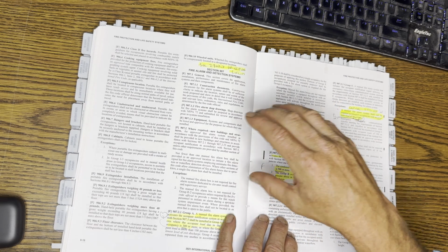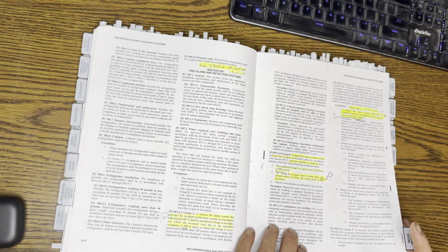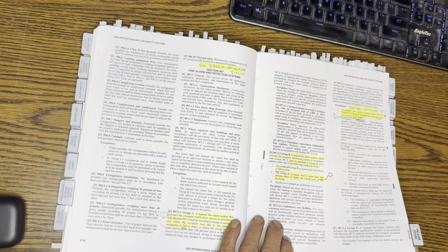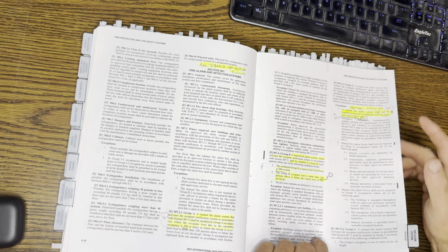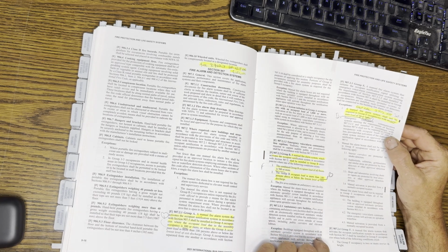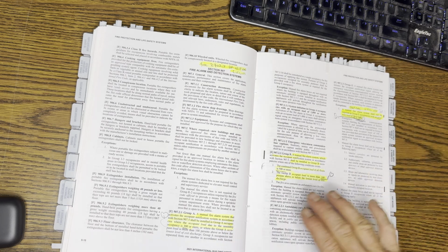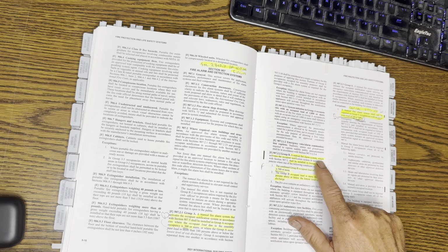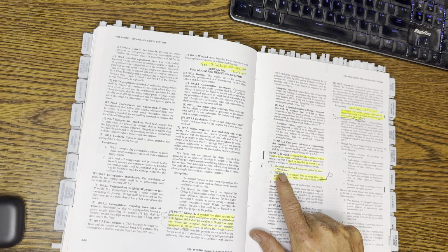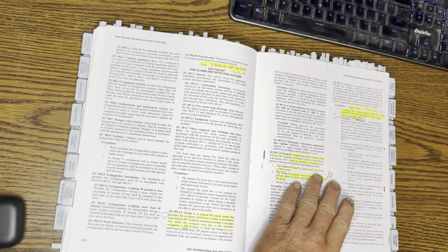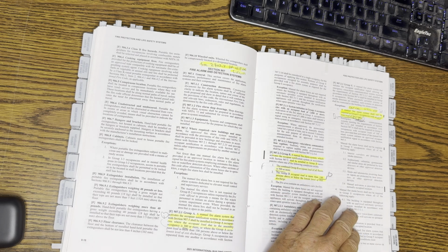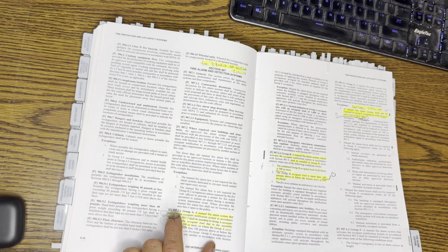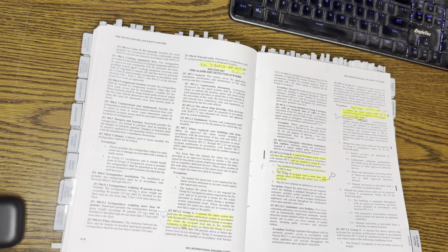A fire alarm system that has individual smoke detectors. And they can all be tied together. If you sense smoke anywhere, then all the signaling devices, the strobes and the alarms go off throughout the structure. So this just tells you where you need it. You don't even need any kind of a fire alarm system, any of them, if you have less than 500 people in a B occupancy. So B occupancies and U occupancies both are fairly flexible. B does require them, but you're allowed to have a lot of people. Group A, you don't need a fire alarm system unless you have more than 300 people.